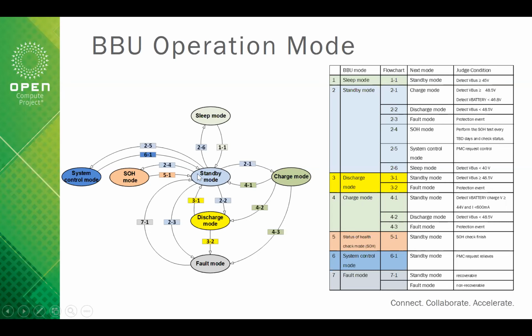When the BBU operates in standby mode or the charging mode, once we find the bus voltage lower than 48.5 volt for 2 milliseconds, we will transfer to discharging mode, and then we provide the power to the IT load. And once the AC recovers, it will go back to the standby mode.